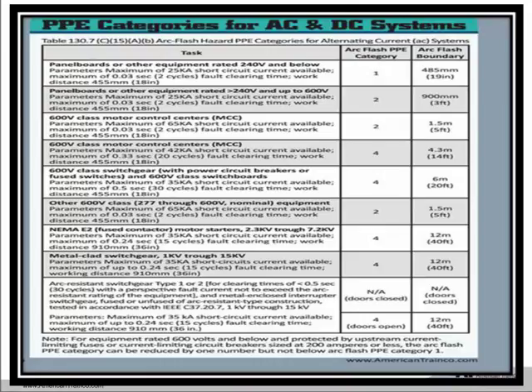If these parameters are easily satisfied, then I can go ahead and use the arc flash PPE category method, and I can find out that I'm under 25,000 amps of fault current. My clearing time of my overcurrent device is 0.03 seconds or less. You can see that the arc flash PPE category would definitely be a 1. And so the next slide that I will show you will tell us what we're going to have to wear in arc flash PPE category 1. It also tells us the arc flash boundary. So we can see the arc flash boundary in this case would be 19 inches.